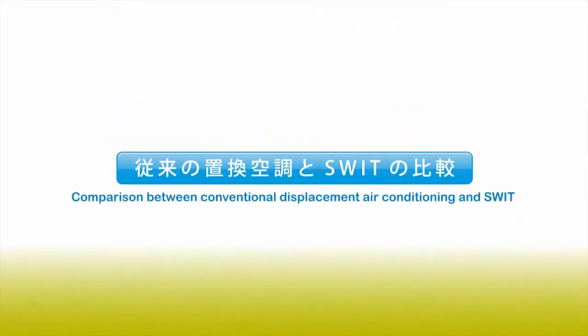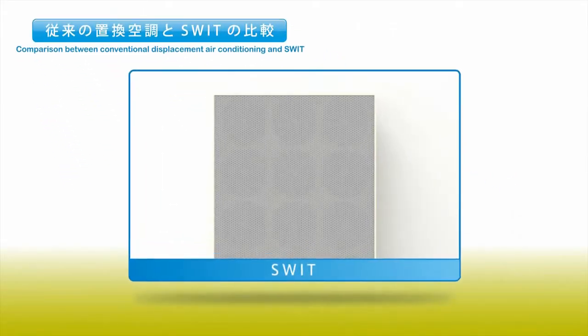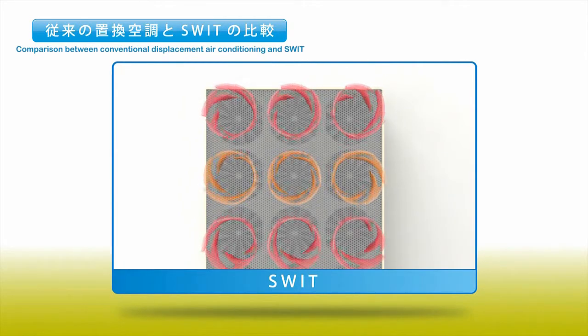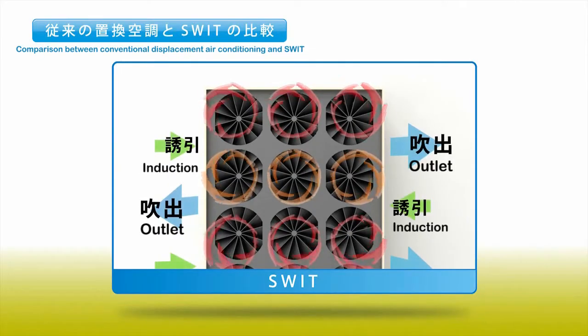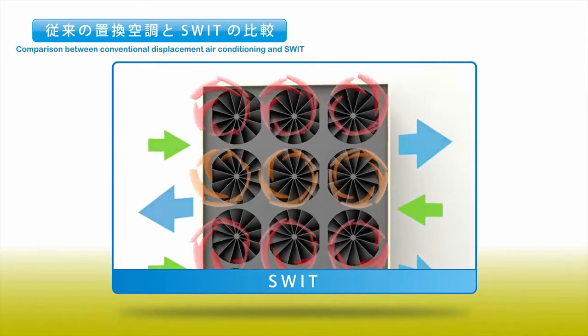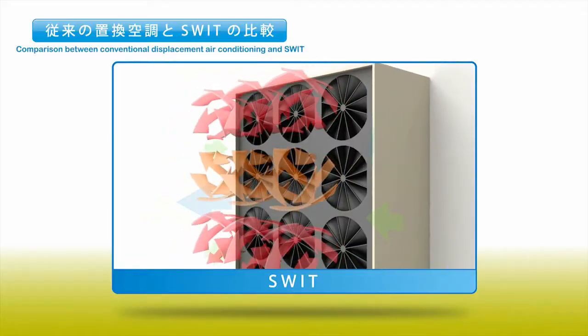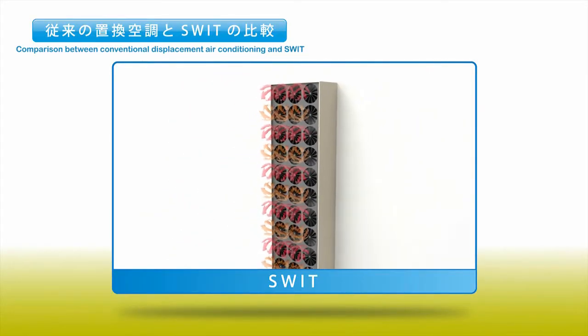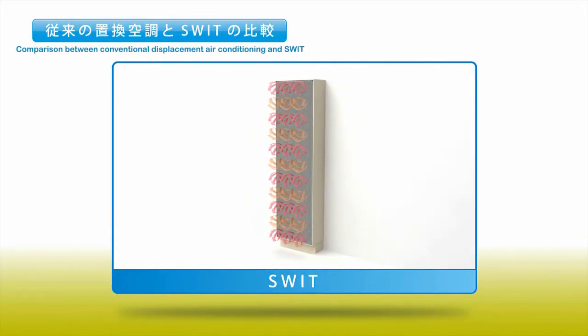Comparison between conventional displacement air conditioning and SWIT. SWIT is a new displacement air conditioning system that uses a swirling flow. Its most striking feature is how it increases the amount of air induction by various combinations of swirling flows. As a result, we managed to improve the level of comfort and cut down the size of the air supply unit to save space.